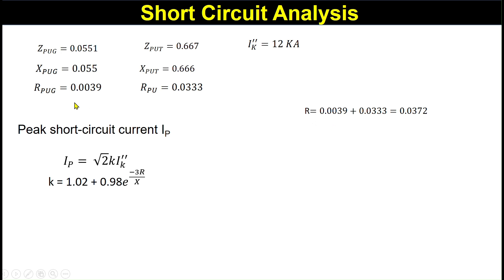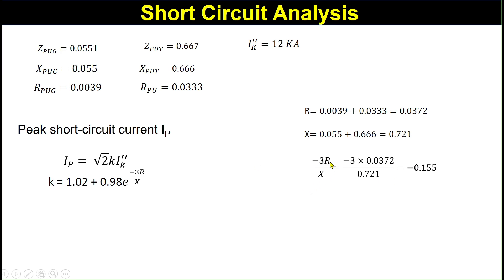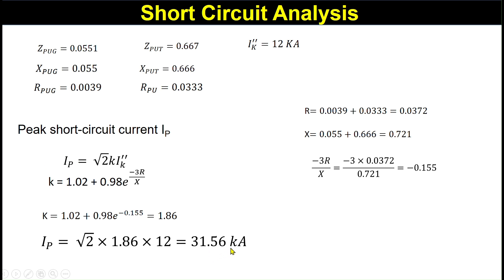Up to the fault point there are two resistances: the resistance of the grid and the resistance of the transformer. The sum of these two resistances is 0.0372. Similarly, the sum of the reactances — the grid reactance and the transformer reactance — is 0.721. The ratio −3R/X equals −0.155. Substituting into the k equation gives k = 1.86. Putting this into the ip equation, the peak short circuit current ip = 31.56 kilo-amperes.